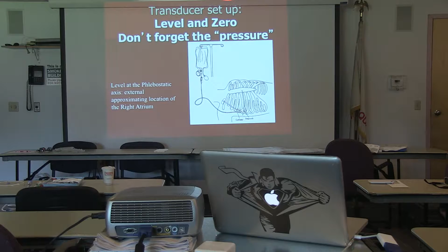Okay. In the balloon pump world, any transducer. Okay, so these are just standards for any of these types of lines here. Keep the tubing length to a minimum. Make sure there's no entrapped air or blood clots, even like we did with the chest tube. Stiff, non-compliant tubing is used, so it feels fairly rigid. Okay, and eliminate any loose connections. So you're going to make sure that everything is tightened down.